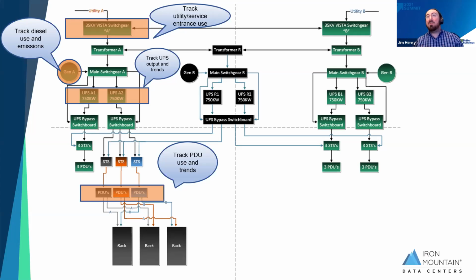It's not really just to talk about how resilient we are, it's to talk about what 50001 will make you think about. If you're a data center, you're tracking your energy use, usually at the PDU level for your IT load, or at the output of the UPSs. That's a pretty good measurement, line loss isn't too bad there, down to the racks themselves.